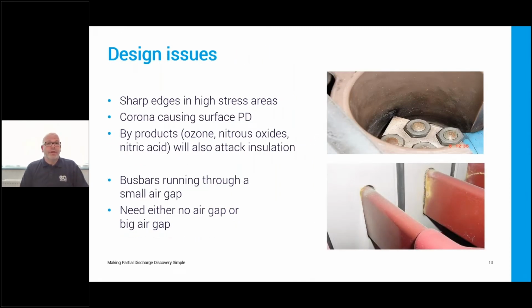Design issues. On the top picture there, one of the things we mentioned earlier was corona discharge, and this picture is an example of how corona can potentially be an issue inside a substation. You can see there's a very sharp edge there in a high stress area, which caused corona PD. And the products of that, so the ozone, as we mentioned before, but a whole host of other things, nitrous oxides, nitric acid, all sorts of horrible things which will attack the insulation. And that's what's happened in that case.